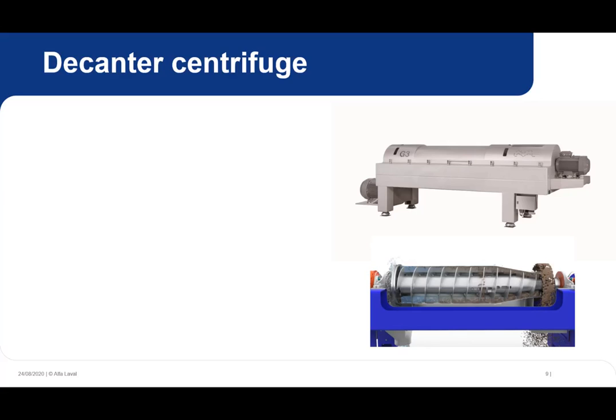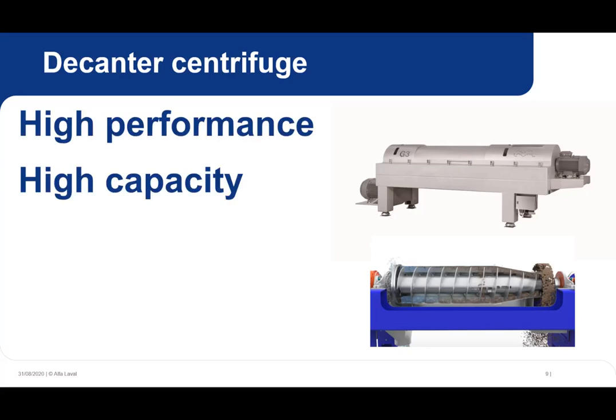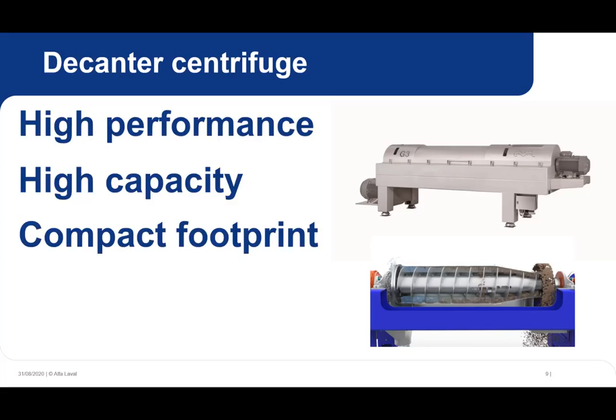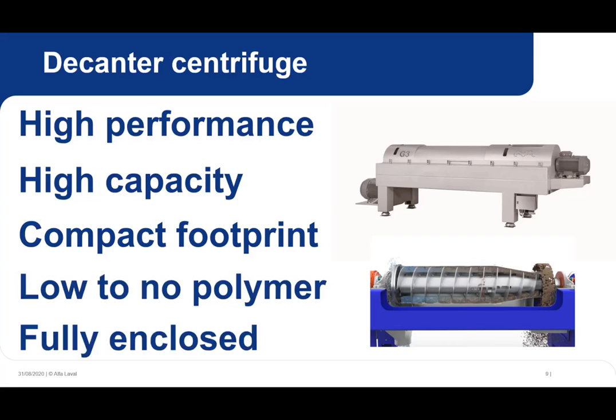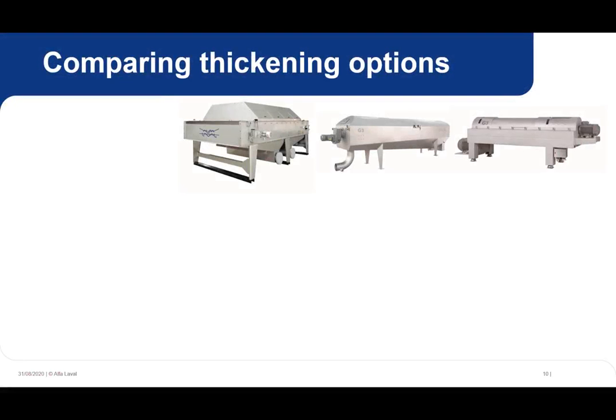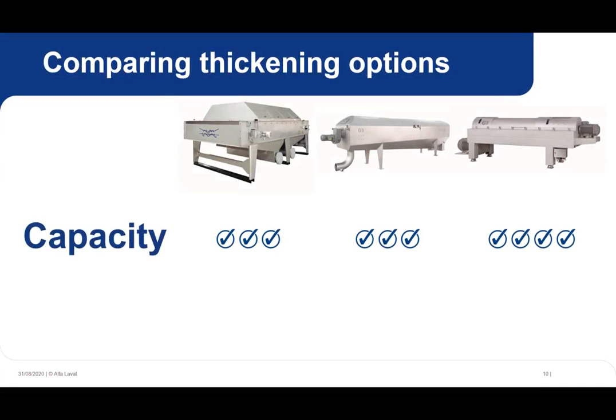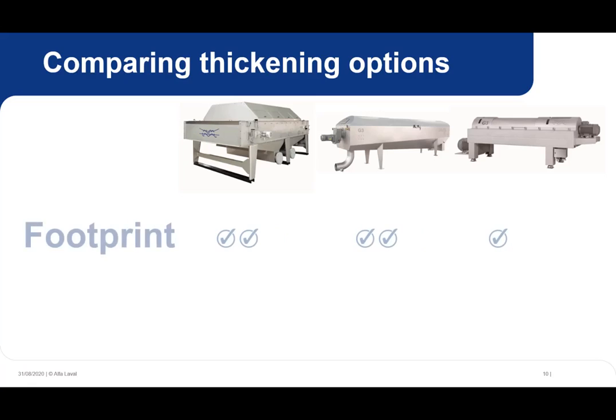Decanter centrifuges deliver high performance and capacity in a very compact footprint. For thickening applications, they use a low amount of polymer and are completely enclosed to provide odor control compared to open equipment. Decanter centrifuges are typically selected for larger plants when the flows would require large amounts of real estate for other technologies. So let's walk through and compare the thickening options. From a capacity standpoint, all three have high capacity, but the centrifuge has slightly more, and with its small footprint, its capacity per square foot of floor space is high.